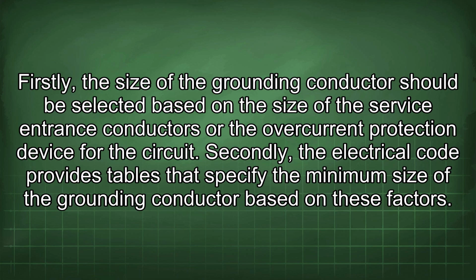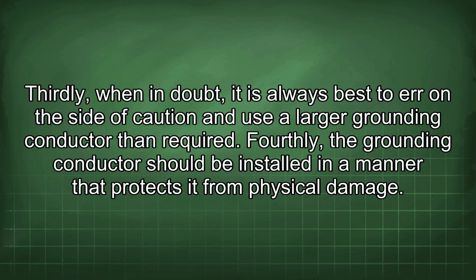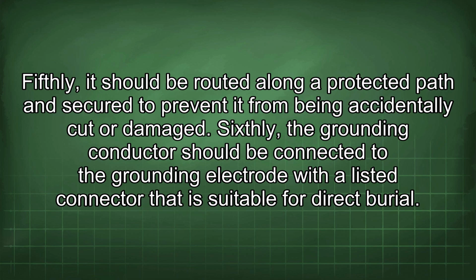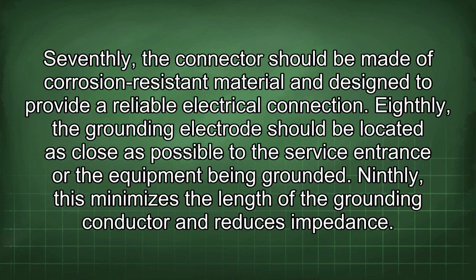Secondly, the electrical code provides tables that specify the minimum size of the grounding conductor based on these factors. Thirdly, when in doubt, it is always best to err on the side of caution and use a larger grounding conductor than required. Fourthly, the grounding conductor should be installed in a manner that protects it from physical damage. Fifthly, it should be routed along a protected path and secured to prevent it from being accidentally cut or damaged. Sixthly, the grounding conductor should be connected to the grounding electrode with a listed connector that is suitable for direct burial.